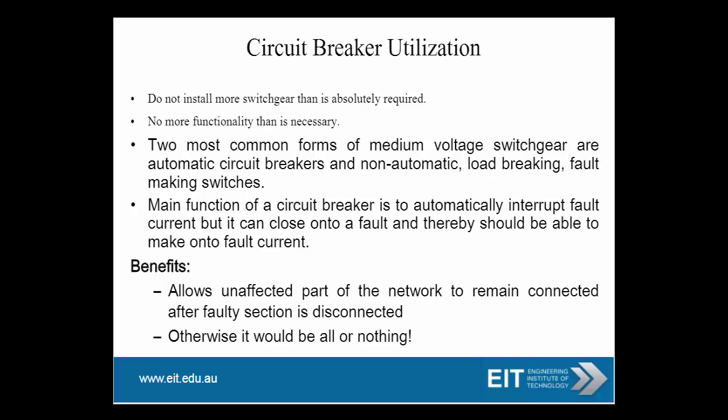The most common forms of medium voltage switchgear are automatic circuit breakers and non-automatic load-breaking fault-making switches. Circuit breakers are automatic — they sense the fault and trip. Switches, however, are manually operated; they don't have a relay. They have the capacity to break on load, but you are physically operating and switching them.